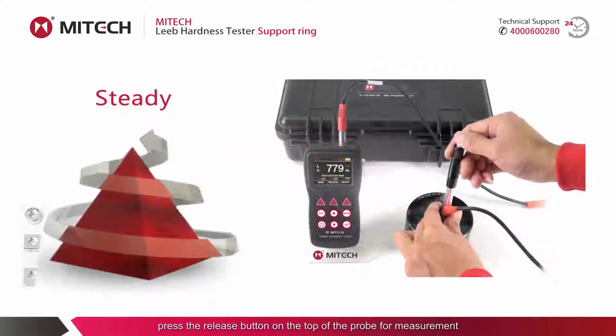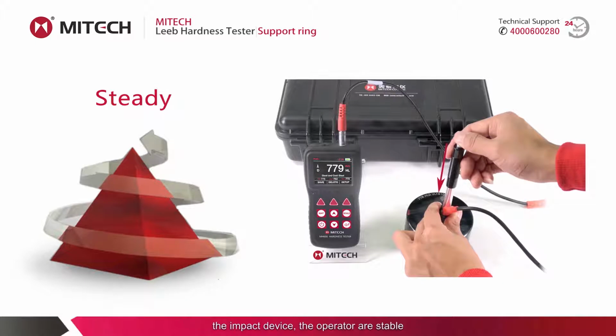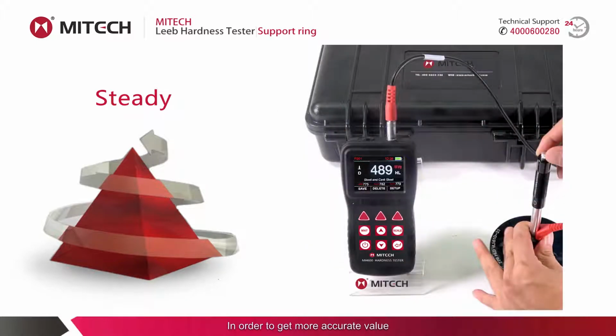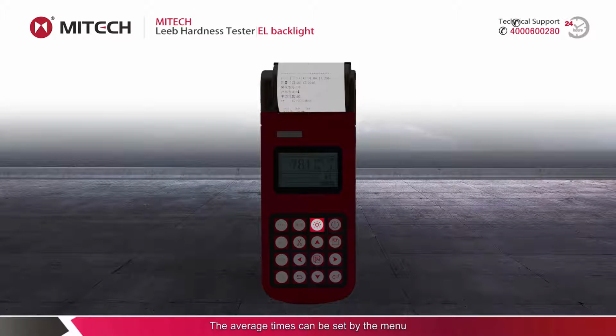Press the release button on the top of the probe for measurement. The measurement process requires that the test piece, the impact device, and the operator are stable. In order to get a more accurate value, the measurement can be repeated several times. The instrument can automatically calculate the average value. The average times can be set by the menu.